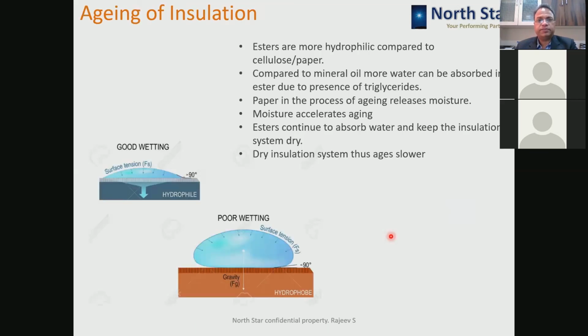Now, let us look at the insulation aging. There is a property of materials as far as moisture is concerned, that is hydrophilic and hydrophobic. The materials which are friendly to moisture are called hydrophilic, and the materials which are not so friendly to moisture are called hydrophobic. So they have a phobia against moisture, so they don't like moisture. Mineral oil is hydrophobic, meaning it is not attracting the moisture, it is repelling the moisture. Your solid insulation, cellulose paper, and esters are hydrophilic, meaning they like the moisture. And ester is more hydrophilic compared to cellulose paper.